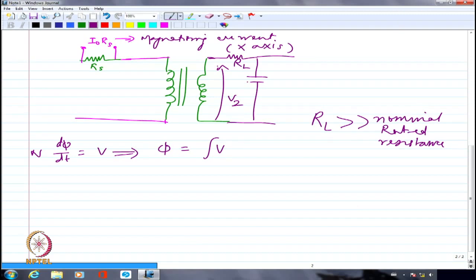Very, very large resistance. Now I have a capacitance also. So if I try to look at what is the current that is flowing here, let me call this some I20 because it is still considered to be no load. Are you getting my point? If I had connected 5.5 ohm, I would have gotten maybe 20 amperes. Now that I am connecting 300 ohms, the current will be negligible, literally. So I am calling that I20 because it is at almost zero load. So I20 is going to be V2 divided by RL plus, or I should say minus, it should not be plus, it should be minus jXC.